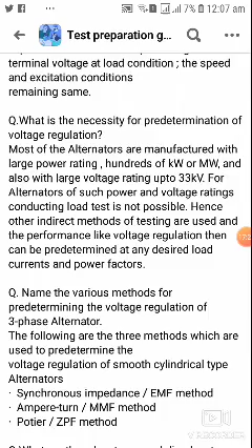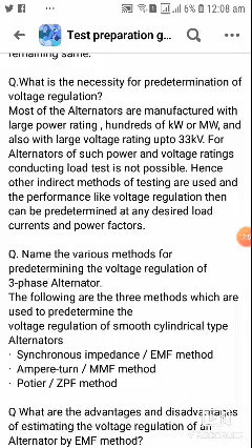Question number 33, what is the necessity for predetermination of voltage regulation? Most of the alternators are manufactured with a large power rating, hundreds of kilowatts and megawatts, and also with a large voltage rating up to 33 kV. For alternators of such power and voltage ratings, conducting a load test is not possible. Hence, other indirect methods of testing are used, and the performance, like voltage regulation, can be predetermined at any desired load, currents and power factors.